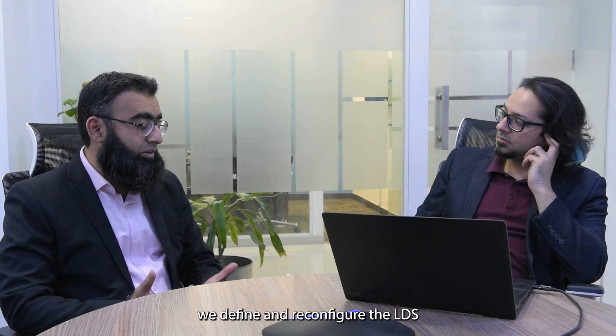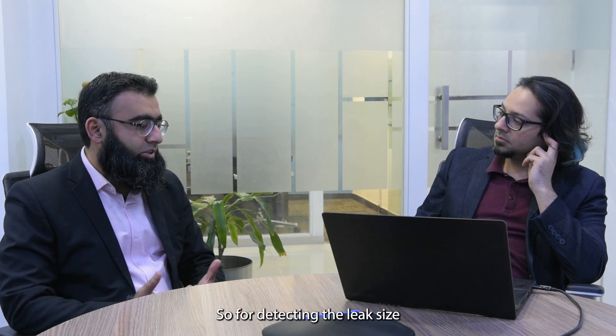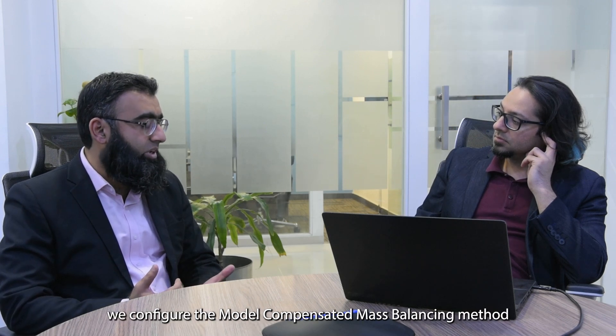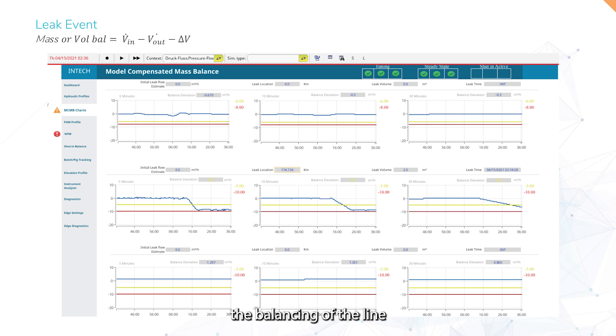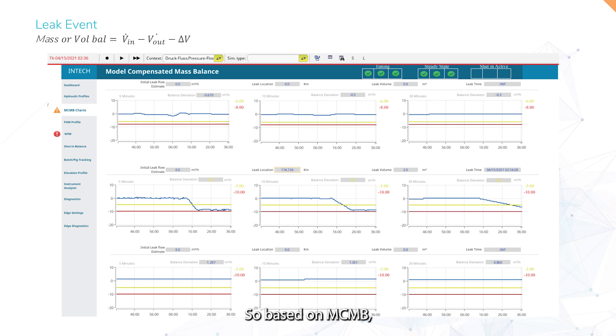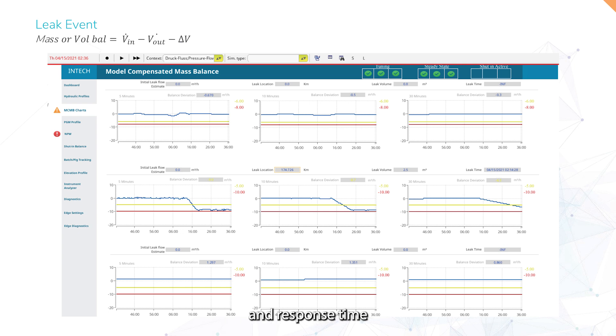Once our simulation and RTTM model is running, we configure detection methods that run in parallel and complement each other. For detecting leak size, we configure the Model Compensated Mass Balance method, or MCMB, which does the balancing of the line by incorporating inflow, outflow, and line inventory changes. Based on MCMB, we determine the leak size and the response time of the system.